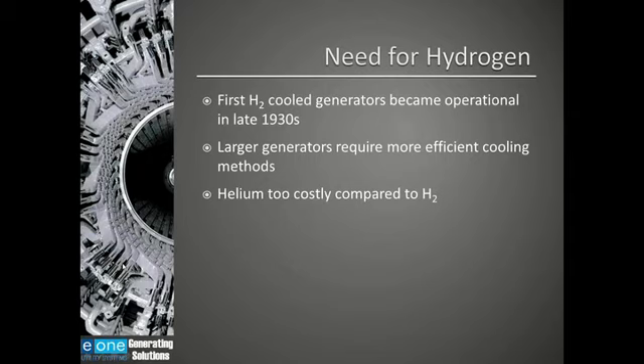In the late 1930s, there was an increasing demand to get more megawatts out of generators. With generators, more megawatts means more iron. They get physically larger and generate more heat. In order to satisfy the demand for power without increasing the physical size of the generator, a different method of cooling was required other than air. Imagine using a very explosive gas like hydrogen to cool a large machine that has components that are spinning at a very rapid speed. I find it very interesting that someone decided it would be a good idea to cool a generator with hydrogen. However, the idea worked, and now all large generators are cooled with hydrogen or a combination of hydrogen and water.